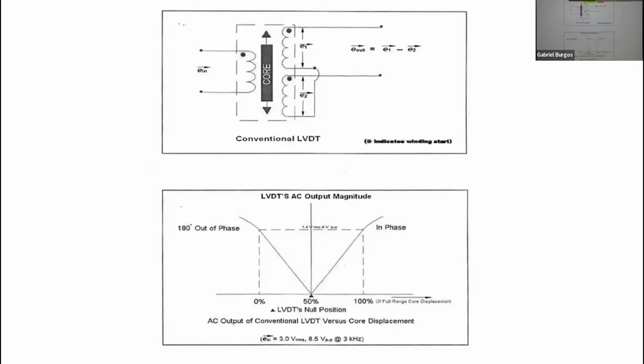They're purely inductive. They don't necessarily have much to do with electronics directly, though indirectly they do. So they're very reliable. They can work in typically terrible environments, like high temperatures and things like that. And because of the way they work, there's a repeatable point, namely the null point, this zero voltage position. It gives you at least some reference of where the core is, if you want a stake in the ground. So it's a very useful tool from that point of view.